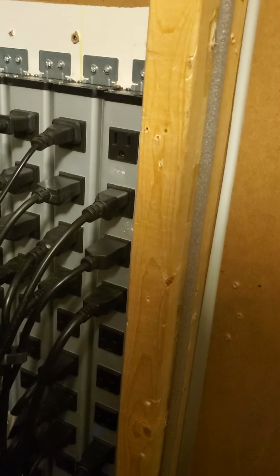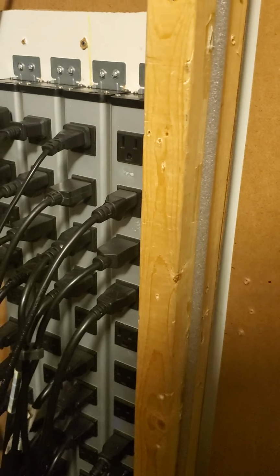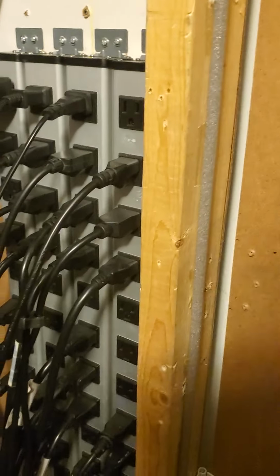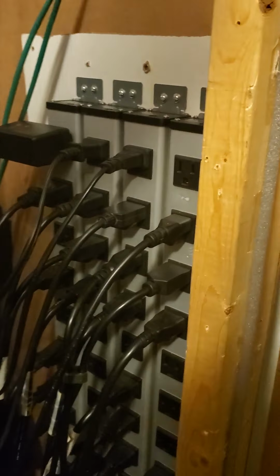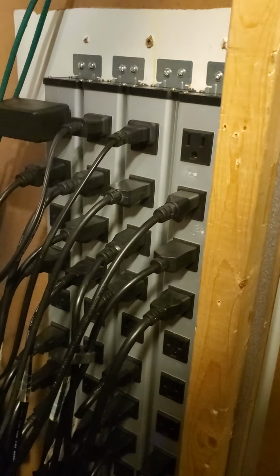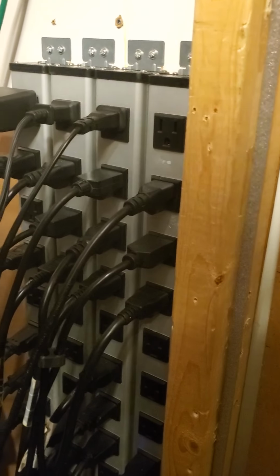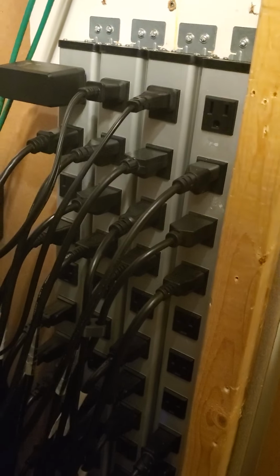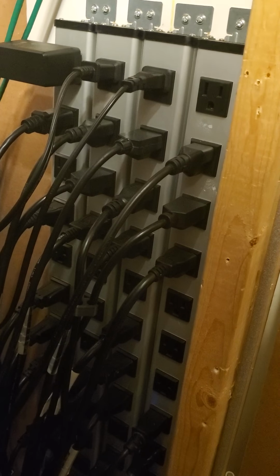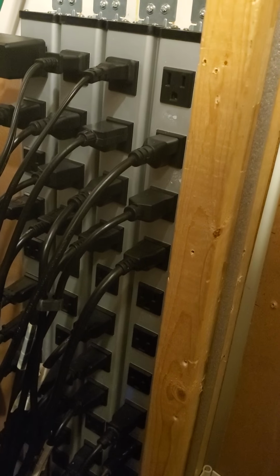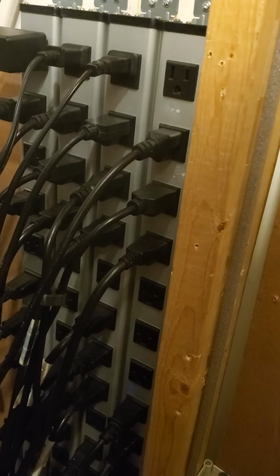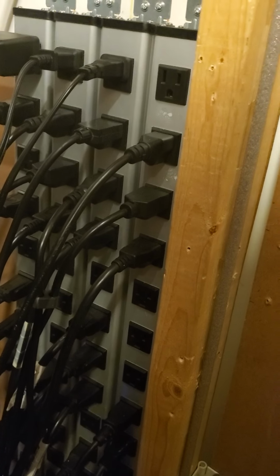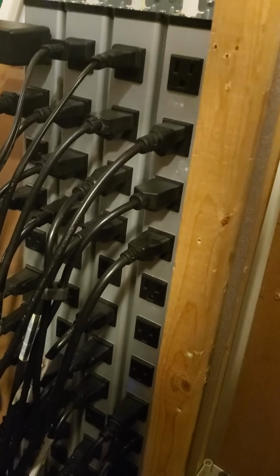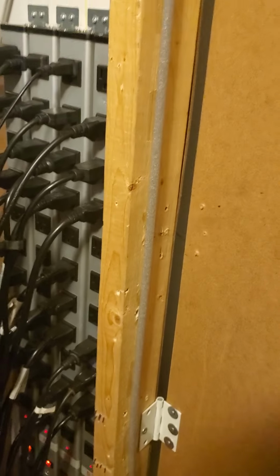And the number they'd give would be wildly off from what the PDU would say. Then I learned a lesson about making sure you use UL rated parts. My inputs on PDU V3 used an IEC power plug that, according to all the documentation, was rated for 15 amps. That's fine, until it wasn't—it turns out it could only take 10 amps. I found that out one day when one of them melted and fused its power switch on, wouldn't trip, and almost burned down my rack.